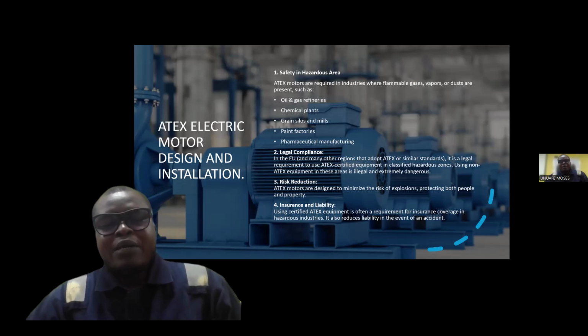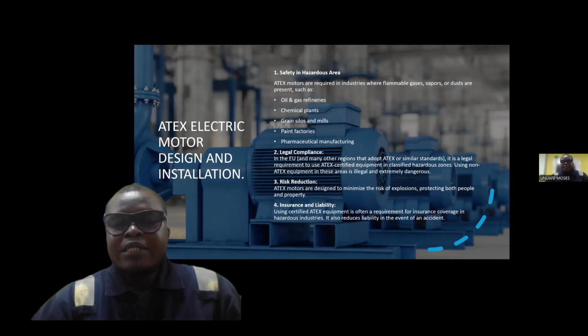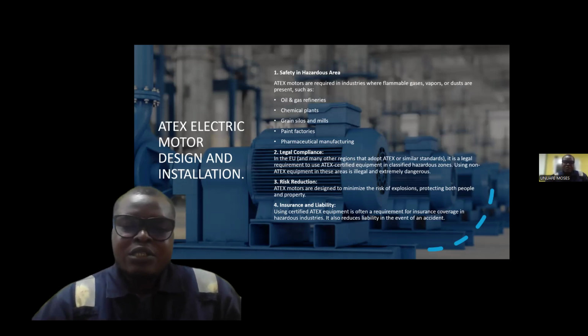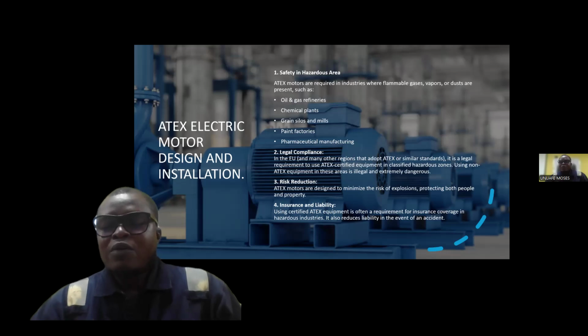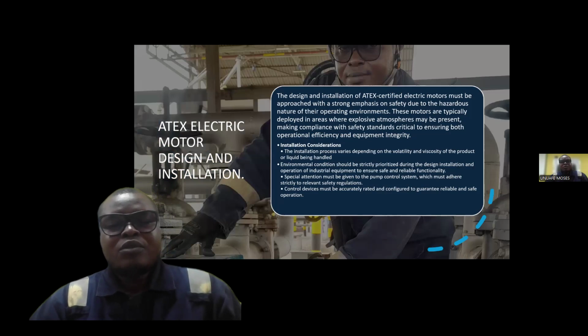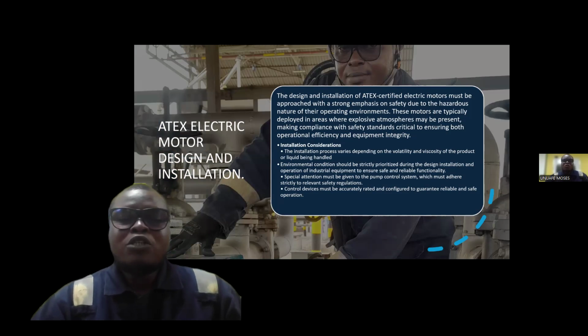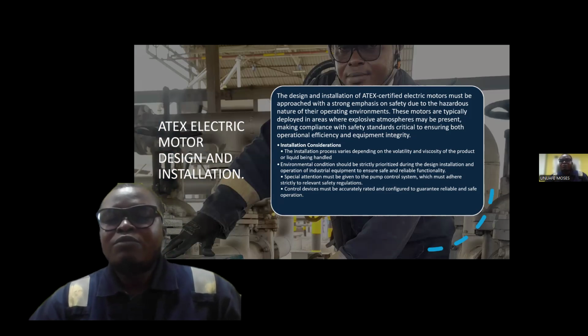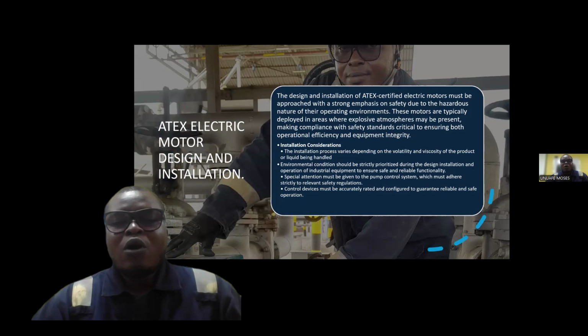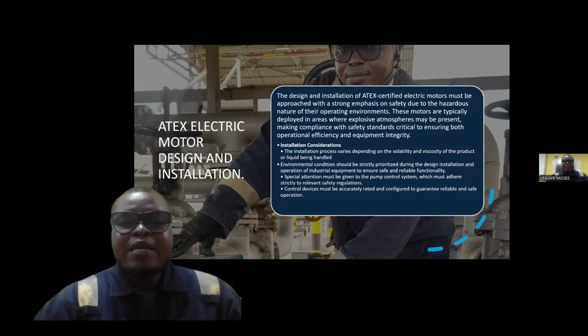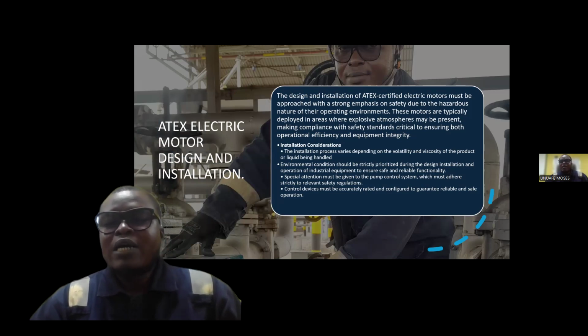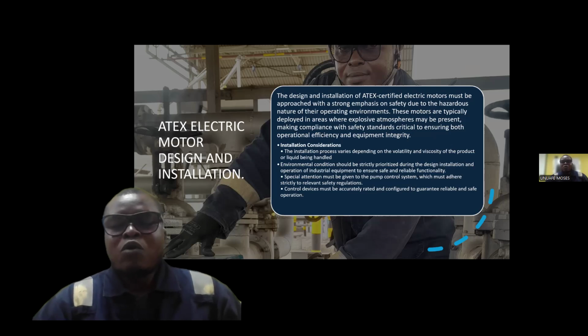What about insurance and liabilities? Using certified Atex equipment is often a requirement for insurance coverage in hazardous industries. It also reduces liability in the event of an accident. I want us to understand that the design and installation of Atex certified electric motors must be approached with a strong emphasis on safety due to the hazardous nature of the operating environment. These motors are typically employed in areas where explosive atmospheres may be present, making compliance with safety standards critical to ensure both operational efficiency and equipment integrity.